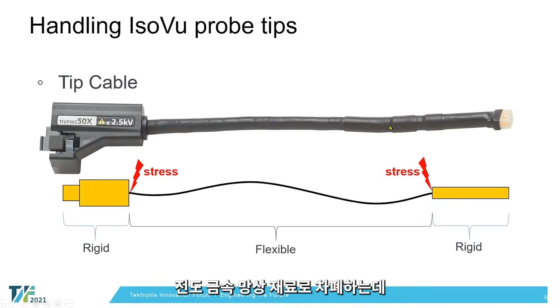And that allows us to basically ground out any EMI fields that may be coupling in around the measurement or around the probe tip and things of that nature. If those are damaged or disrupted in any way, that can cause failure. So it's really important to keep in mind that these tips are flexible, but they need to be taken care of and not just thrown into drawers and things like that.